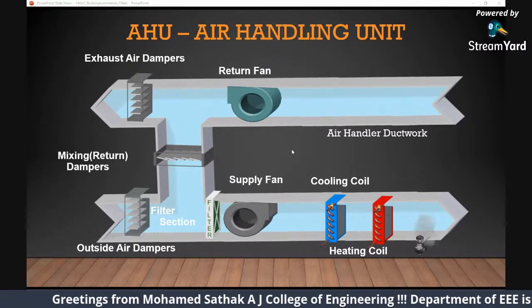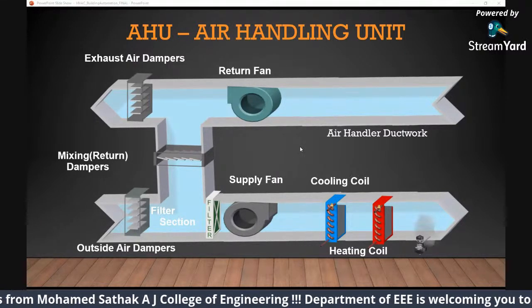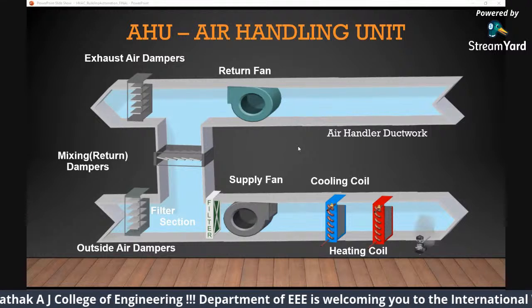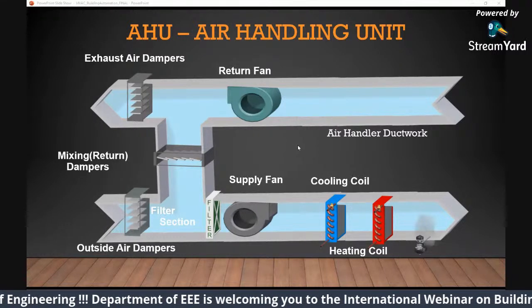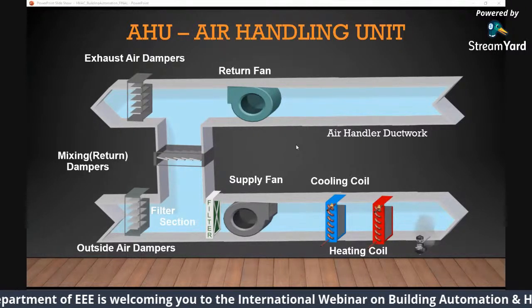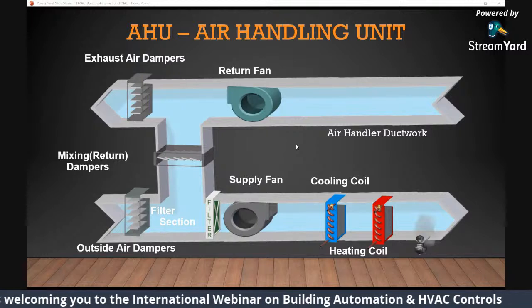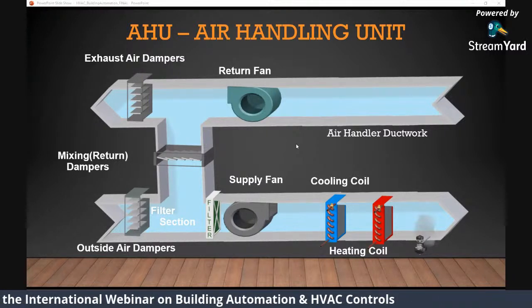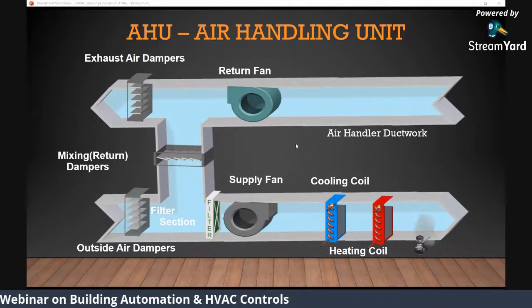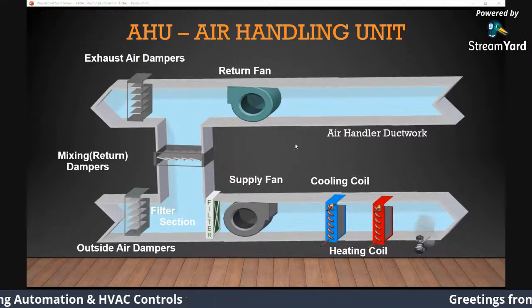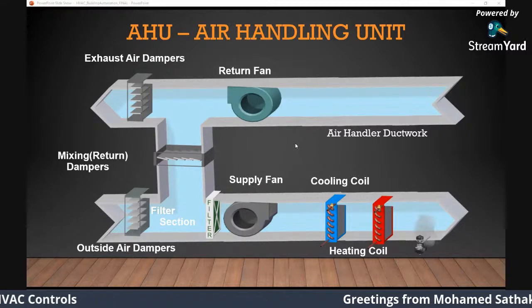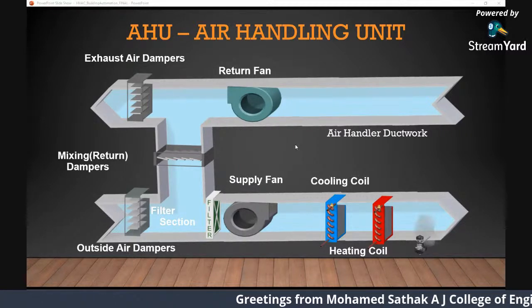If it's too hot outside, you want to keep the human beings at 21 to 25 degrees Celsius. You run the AHU, your chiller supplies chilled water to your cooling coil, and you get cold air to maintain the perfect temperature level. Now, if it's too cold outside, you'll run the boilers. You supply hot water to the heating coil, and it gets you your comfort zone. So that's the complete principle behind it.